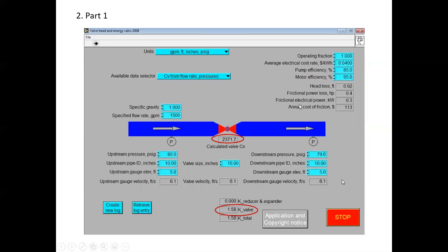So we put all that stuff in. And we've stuffed in the operating fraction and the electrical cost, and these are just some nominal values for pump efficiency. I mean, we could go put in better values, but we're not really using this right now to look at the cost of the friction. So what we're really doing is wanting this to calculate the CV for the valve. So in that case, it doesn't matter what you put in here, but those are probably a little high on pump efficiency, but motor efficiency is about right. Okay, so I plug all this stuff in. Upstream pressure 80, downstream 79.6. Everything is 10 inch. The gauges are at the same elevation, so that'll cancel out. My flow rate, specific gravity, and bingo.